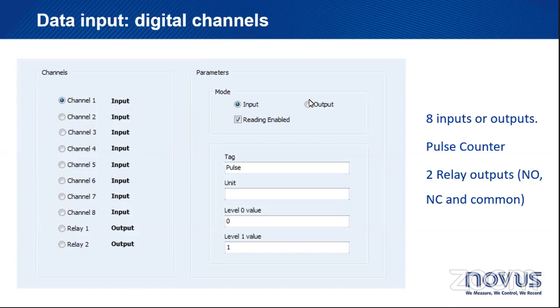First, they can act as an alarm output. So if I have a logic, an alarm logic there, okay? And my logic says, if temperature is above 300 degrees Fahrenheit, I want an output to come on. That is a possibility. The FieldLogger has all those eight digital IOs plus two relays that can act as outputs for alarm.